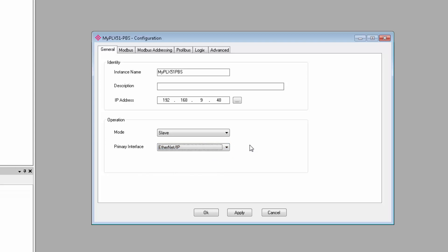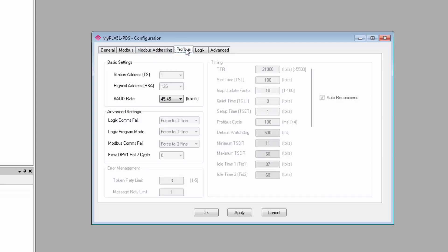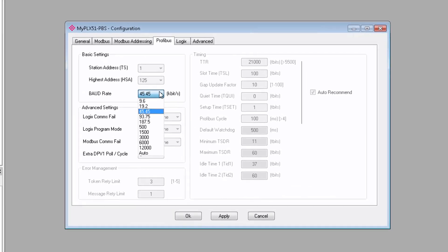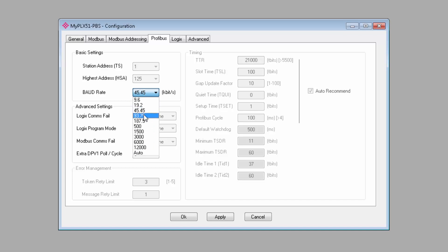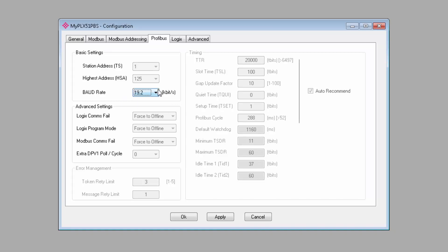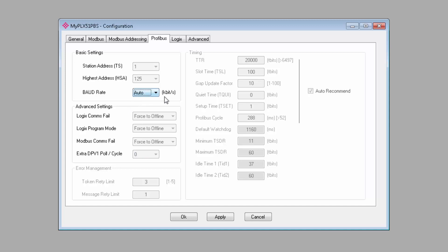We'll move on to the Profibus tab. As you would expect, this is where you configure your Profibus network parameters. We have several sections, but for the slave mode, all you need to do is set the baud rate. If you already know what baud rate your Profibus master is set to, you can pick that specific rate. Otherwise, auto mode will detect the rate of the master and adjust the module baud rate accordingly. And you can click Apply when you're done.